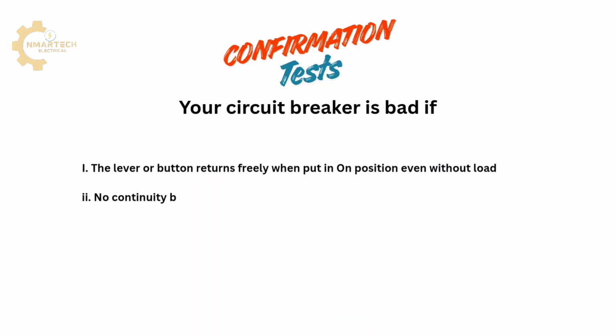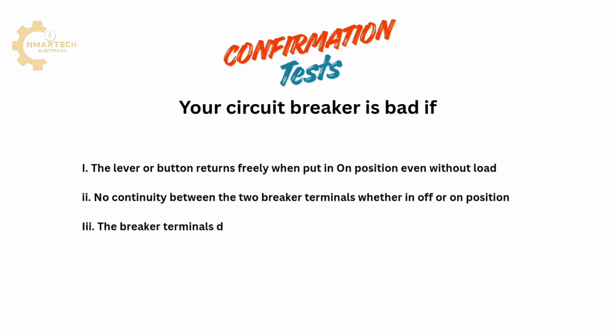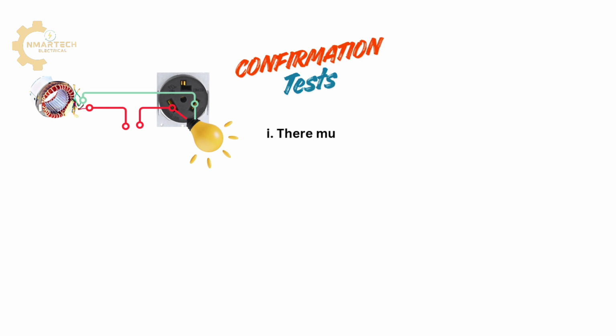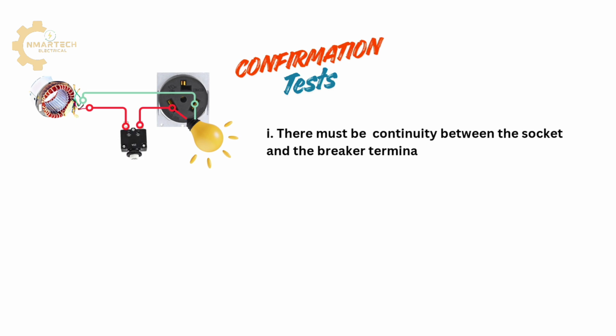2. There's no continuity between the breaker terminals, whether it is on or off. Normally there should be continuity between the breaker terminals and the socket. When there is no continuity between these points, know that your breaker is bad. And this is revealed by a continuity test with a multimeter. How do you confirm? There must be continuity between the socket and the breaker terminals. Please remember to conduct this continuity test when the generator is off.